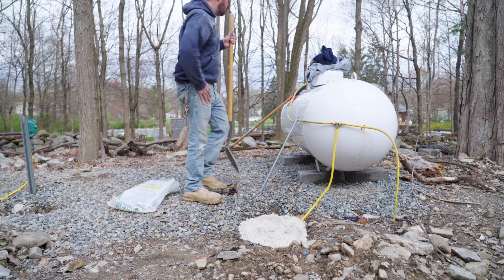It will power our entire panel with priority given to the air condensers for the HVAC system and our hot water heater. It will sense the loss of utility power and immediately crank on the standby generator and switch the panel over automatically using the transfer switch, so you have a loss of power for maybe about 60 seconds before the generator kicks on and energizes your whole panel. As soon as the electrical grid is restored, it will sense that, shut off the generator, and reroute power from the utility back to the panel again.